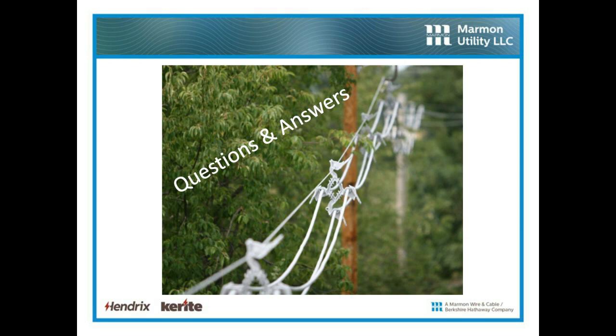I mean, if you've waited to do tree trimming until you've got a 6-inch limb sitting on the cable, you probably have held off tree trimming too long. Hopefully that limb is sitting on the messenger, in which case you don't have a problem at all. Utilities have told us that they're saving 80% of the tree trimming, number one, and number two, they're doubling the cycle. So if they have a two-year cycle for bare wire, they're tree trimming spacer cable every 4 years. And some of our tropical clients, whether that's Panama City or Brazil, they have 12-month tree trimming, so they're spacing that out to 24 months now with the spacer cable.